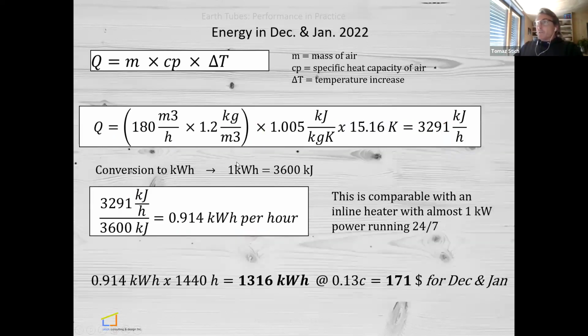So, coming to some calculations. I calculated for December and January the equivalent preheater that would have been required to preheat the air to this temperature. That's the formula, M being the mass of air, Cp specific heat capacity of air, and the delta T, based on the numbers that I just showed you. So this is the mass of air, this is your specific heat capacity of air, and this is my delta T in average. So that's 3,291 kilojoule per hour. If we convert this into kilowatt hours, it would be 0.914 kilowatt hour per hour, right?